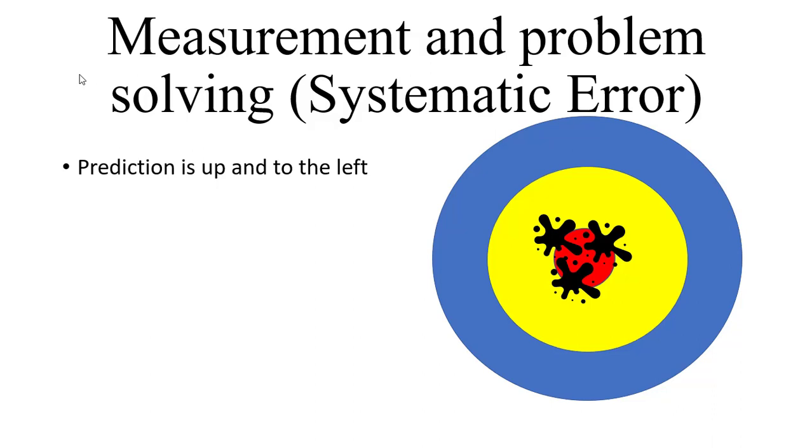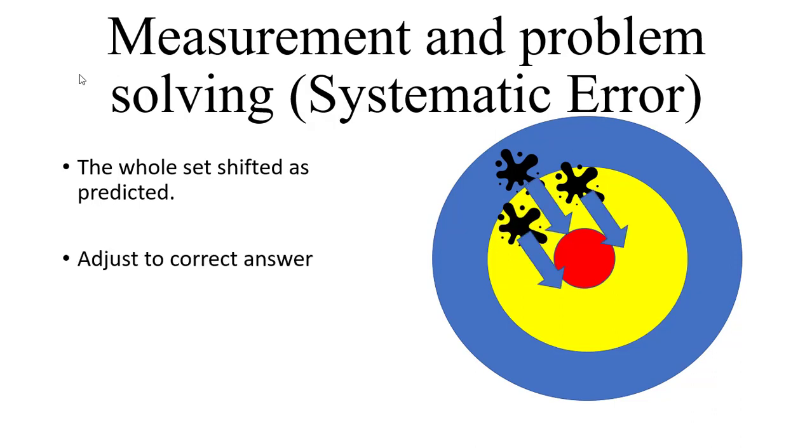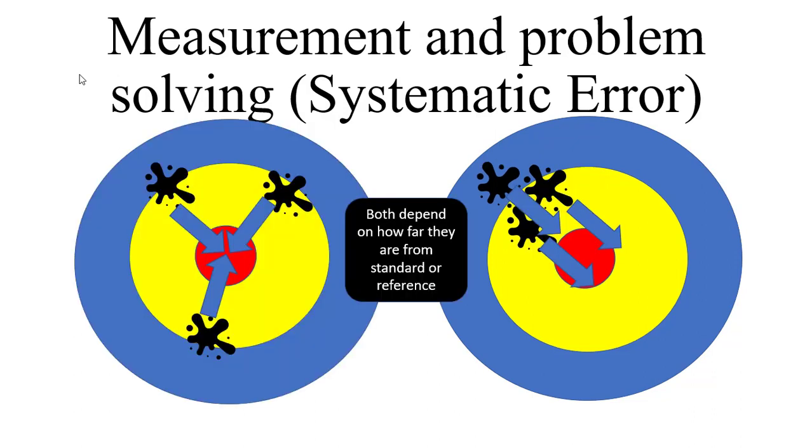Systematic error tends to shift all measurements in a systematic way so that in the course of a number of measurements, the mean value constantly varies in a predictable way. When a calibration is being carried out from a reference specimen, these systematic errors are corrected. An example would be when a pH meter probe gives consecutive readings that are all too high or too low, and the device is adjusted to show the correct reading.